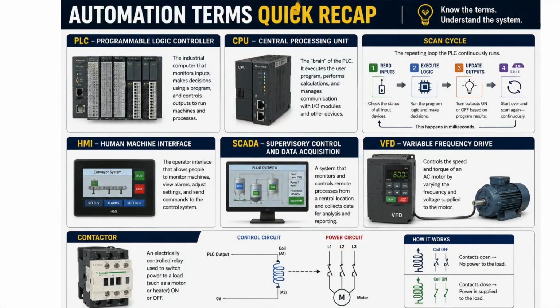One more before we move on. A conveyor won't start. Run lights on. Start button works fine. What do you check first? The CPU, the output LED, the contactor coil, motor voltage, or the overload relay? The output LED. Run lights on, and the button works. So the PLC's scanning fine and got the input no problem. Fastest next check is whether that output LED is actually energizing. That tells you if the PLC is even commanding the output before you go chase the contactor, motor voltage, or overload relay downstream.